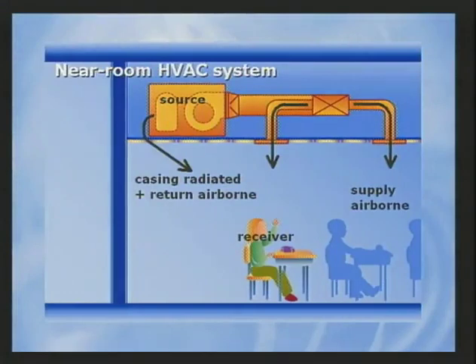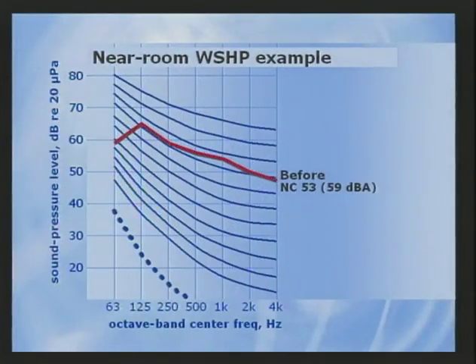Without any acoustical consideration, the unit might get located in the plenum over the classroom as shown here. The supply duct in our example runs 10 feet, splits at a T-junction, and runs an additional 10 feet to the two diffusers. To improve this application, the unit is moved out of the plenum space into an adjacent room. The supply ducts were lined, and a lined return duct that terminates in the plenum space above the room was added. This slide shows before and after sound predictions.